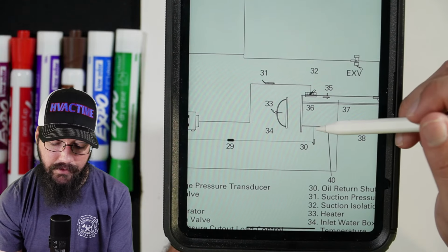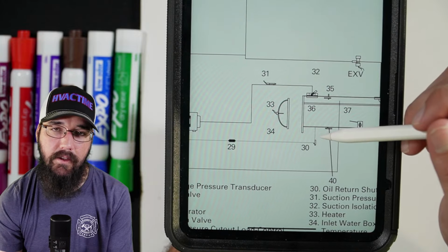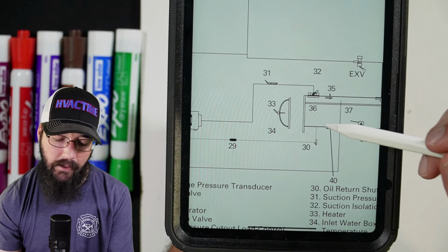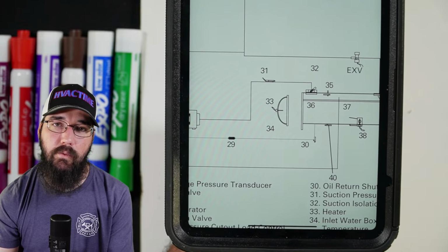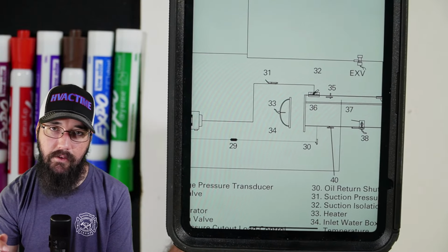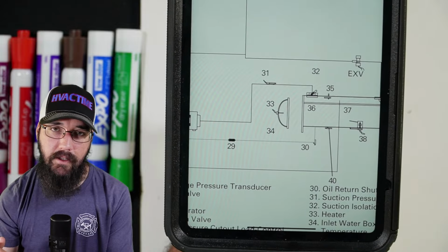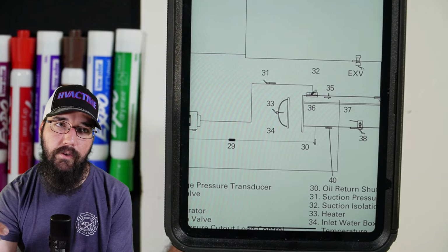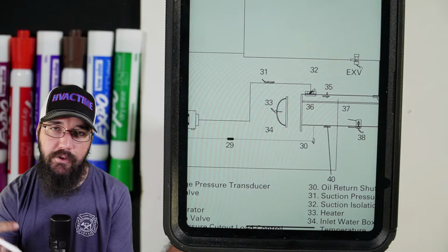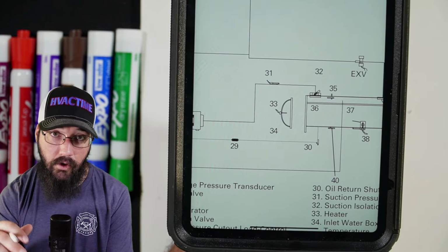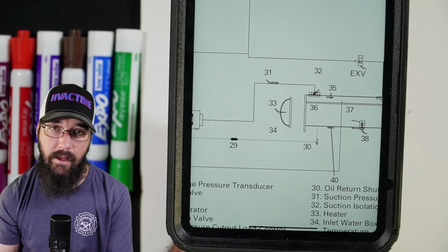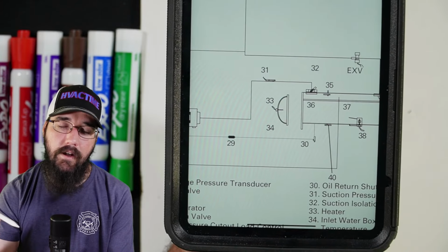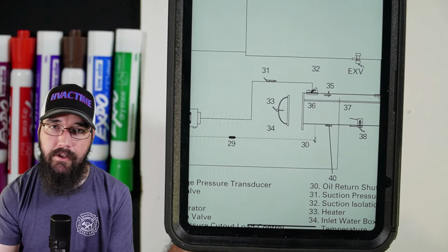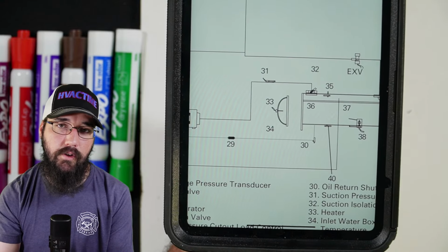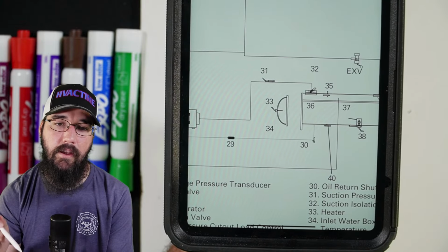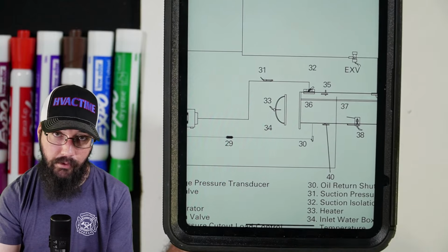Well, that's where we have this return line off the bottom of the evaporator on these. And it can be on the bottom because that is where the liquid refrigerant is. These machines maintain a very low liquid refrigerant level, and when the machine is running, our oil recovery circuit, or oil return circuit as this manual describes it, only works while the machine is running. So our oil return circuit doesn't do anything when the machine is off, or when the compressor is off.